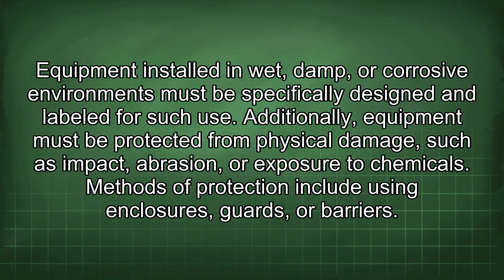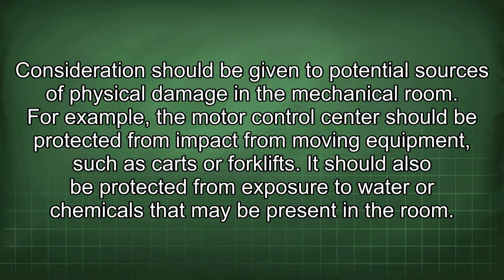Equipment installed in wet, damp, or corrosive environments must be specifically designed and labeled for such use. Additionally, equipment must be protected from physical damage such as impact, abrasion, or exposure to chemicals. Methods of protection include using enclosures, guards, or barriers. Consideration should be given to potential sources of physical damage in the mechanical room.